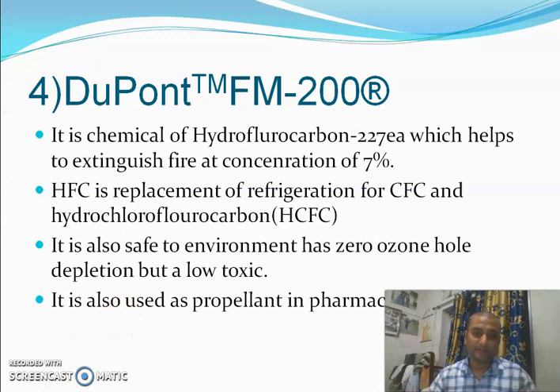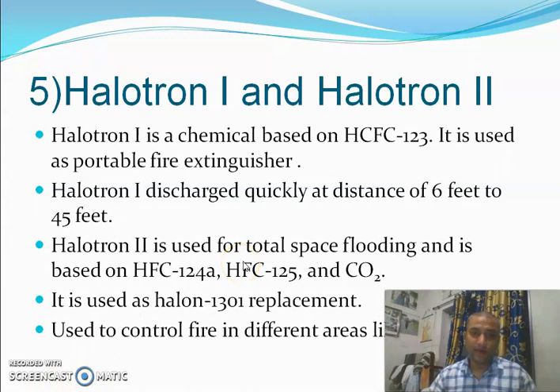Moving to the next topic: Halotron 1 and Halotron 2. Halotron 1 is a chemical based on HCFC-123, used as a portable fire extinguisher, discharged quickly at a distance of 6 feet to 45 feet. Halotron 2 is used for total space flooding, based on HFC-124a and HFC-125 and CO2. It is used as a Halon 1301 replacement, to control fire in different areas like IT industries.